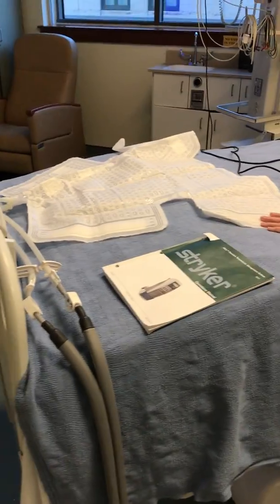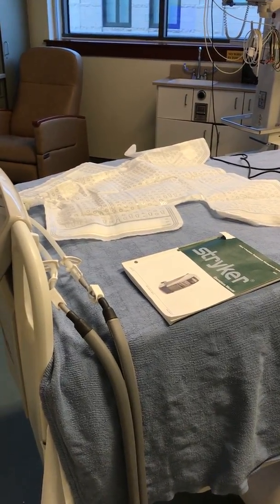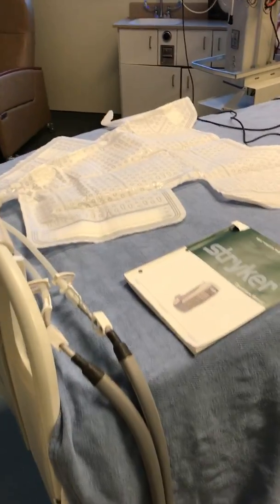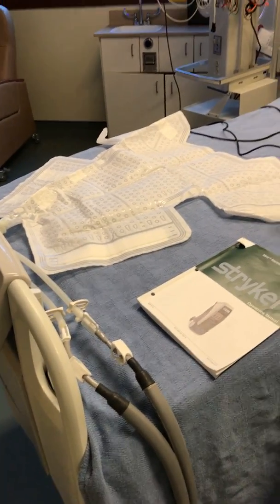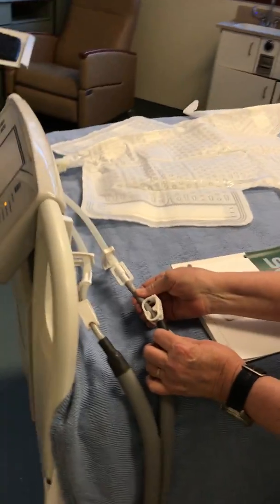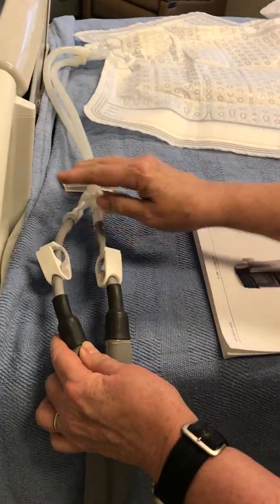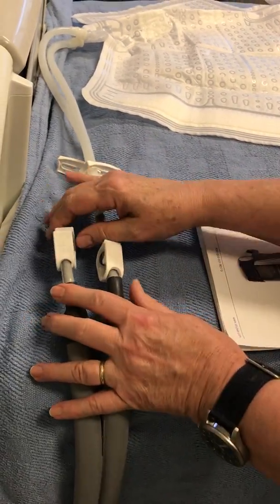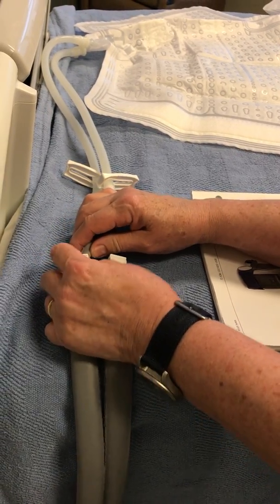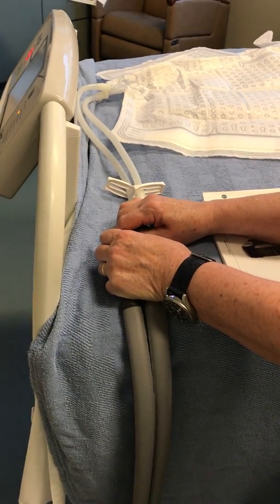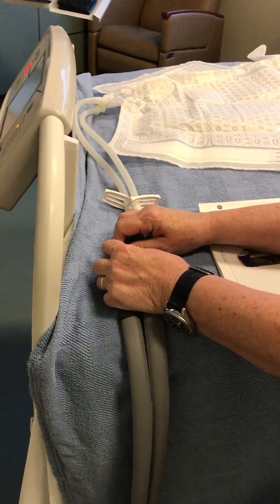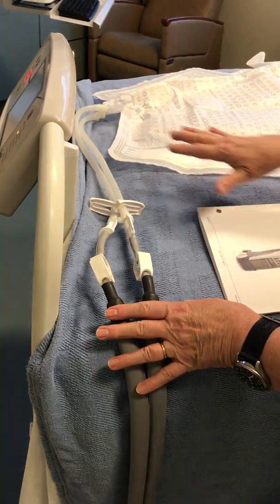You'll have your pads all set up and ready to go to be inflated. You have to fill these with water before you can place them on the patient. Make sure there are no kinks in your tubing. Everything's open. If there is any kind of a kink, the machine will show an error. If there's an error, only Biomed can fix that. So just confirm that there are no kinks.